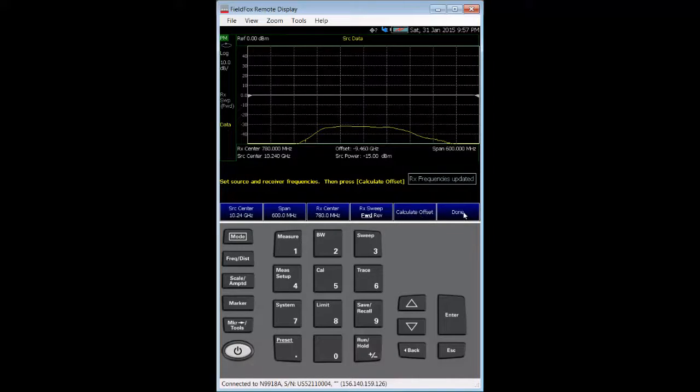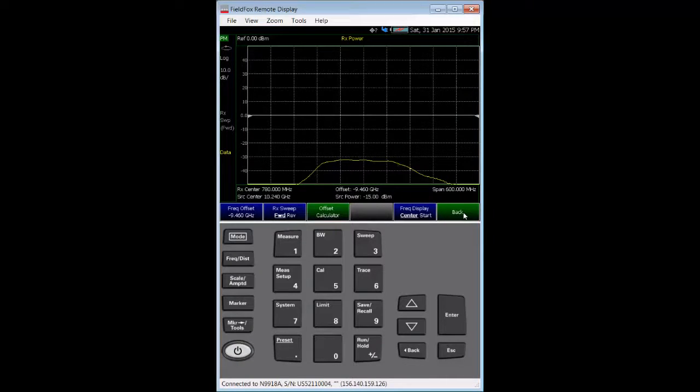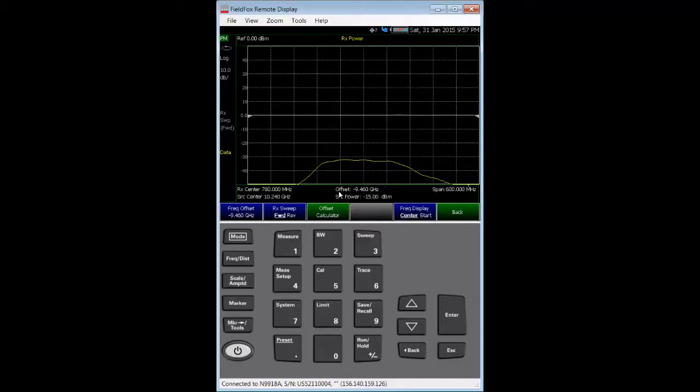Then, I poke the calculate offset soft key. After that, press done. And then, we'll set the frequency offset at the bottom of the graticule is calculated to be negative 9.46 GHz.